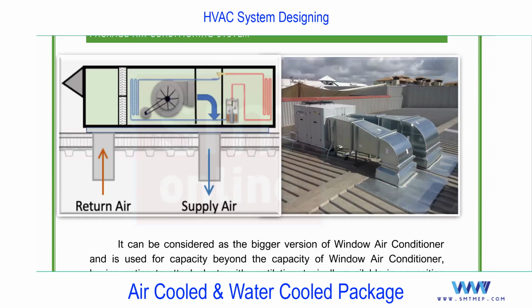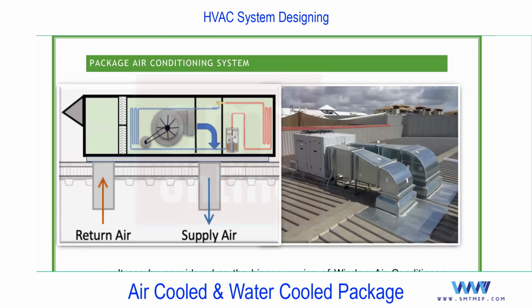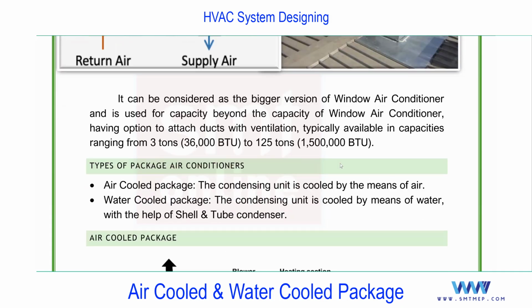If you do not use the return duct, what will happen? The suction will be of the complete outside air, and outside air is hot and humid in summer. So that will directly increase the load on the cooling coil. The fresh air is hot and humid, and if you completely use fresh air without return air, what will happen? The load on the cooling coil is going to be more than double, because remember, the heat gain through ventilation is also one of the major sources of heat gain in summer, and in winter also for a heating system, but at this level I'm talking about the cooling system. So return is required. How exactly?